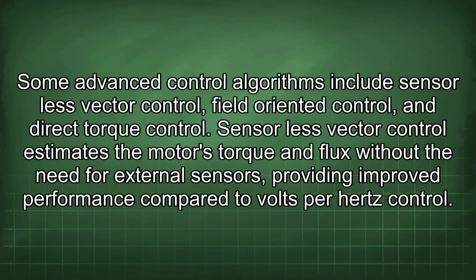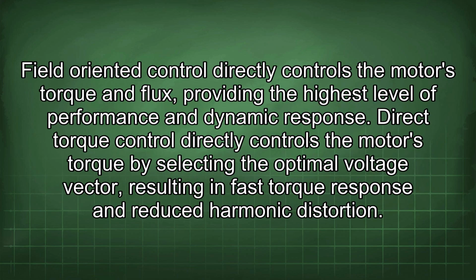Sensor-less vector control estimates the motor's torque and flux without the need for external sensors, providing improved performance compared to volts per hertz control. Field-oriented control directly controls the motor's torque and flux, providing the highest level of performance and dynamic response. Direct torque control directly controls the motor's torque by selecting the optimal voltage vector, resulting in fast torque response and reduced harmonic distortion.